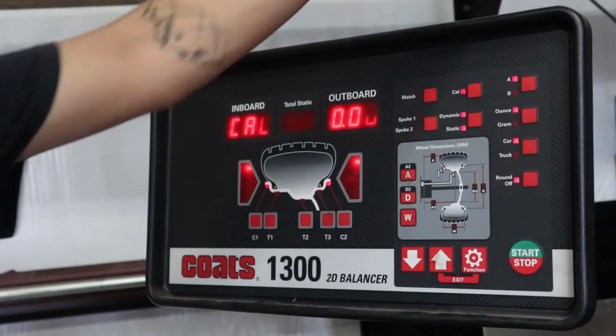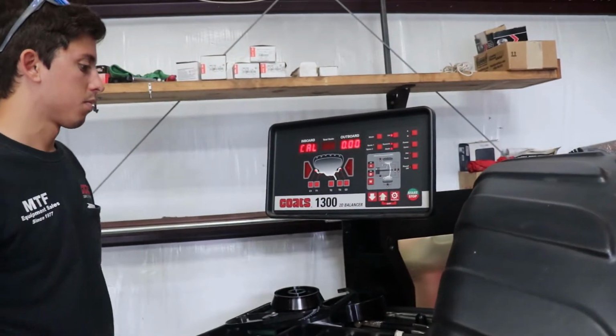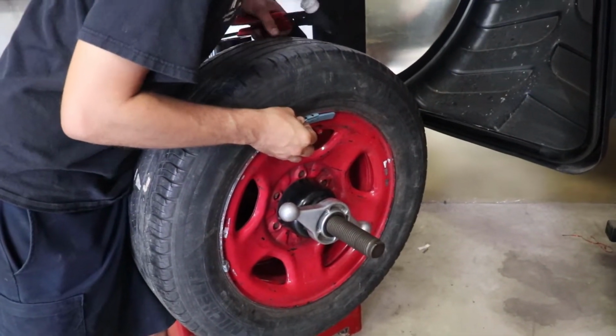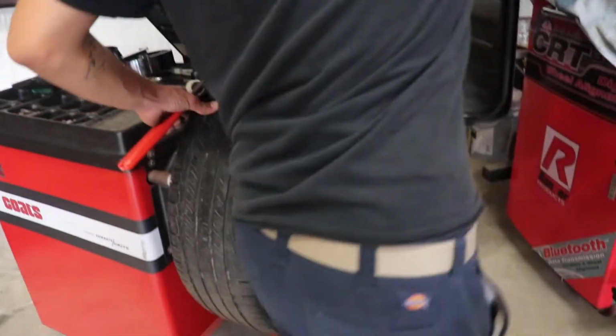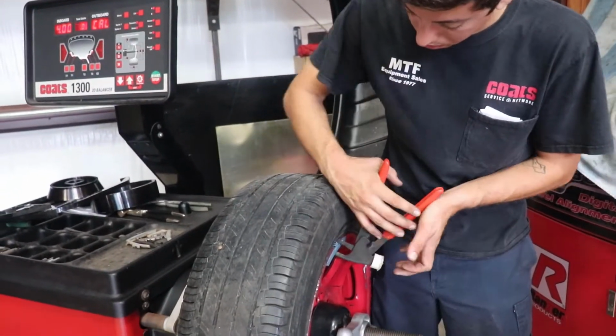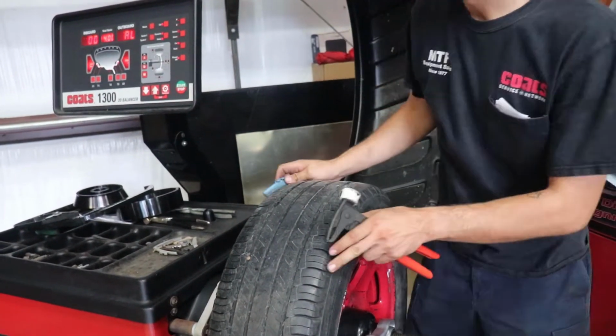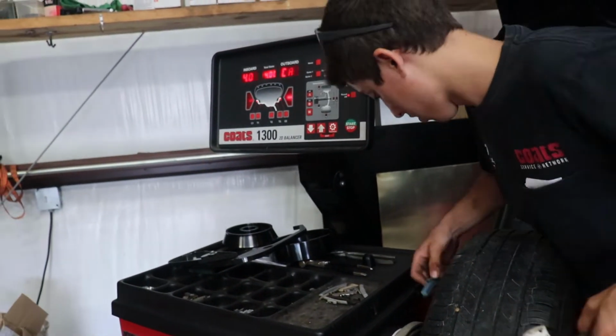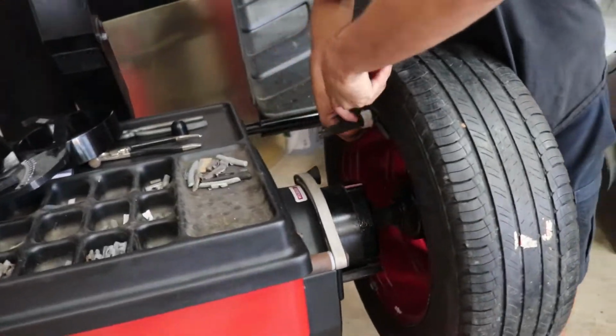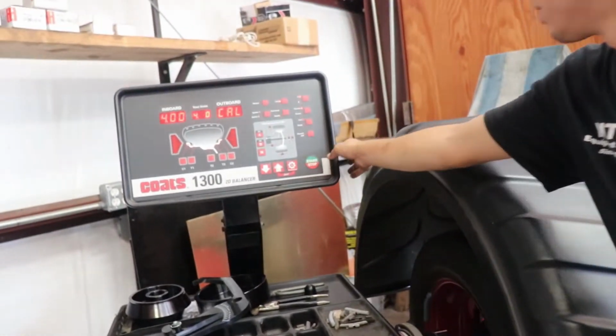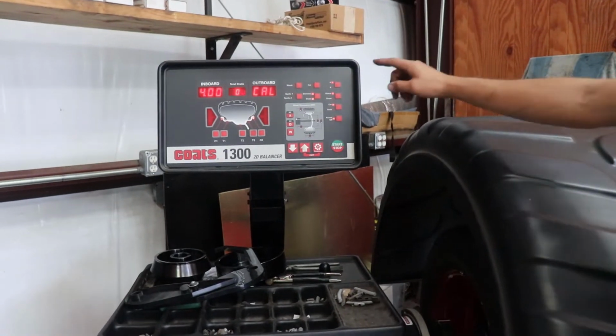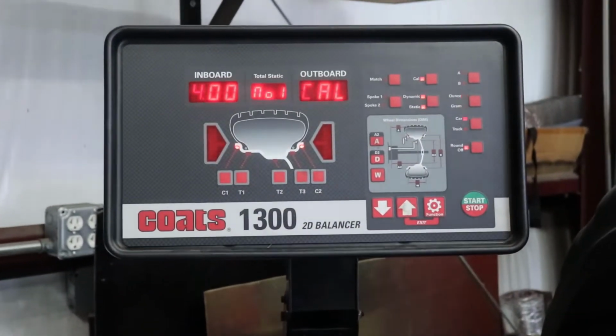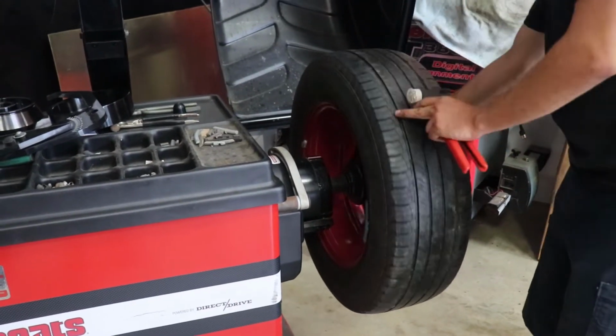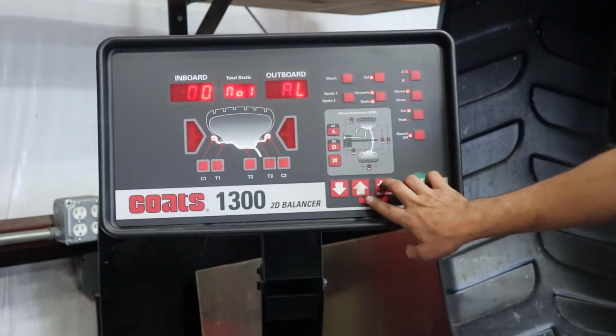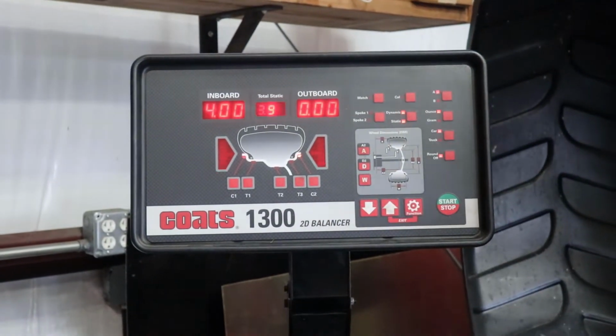Calibration. The machine does everything it can to try and walk you through the process. So if you can read some of the hieroglyphs that it gives sometimes, you can tell what to do. After the second spin, it'll say end, no one, which is no errors, and then it should cycle to end. And after that, you hit your exit again, which is your function, and your up arrow. Then you can take your calibration weight off.